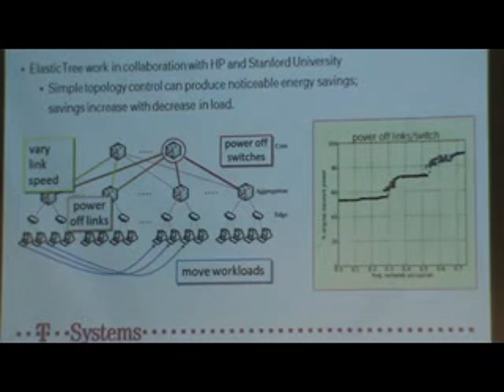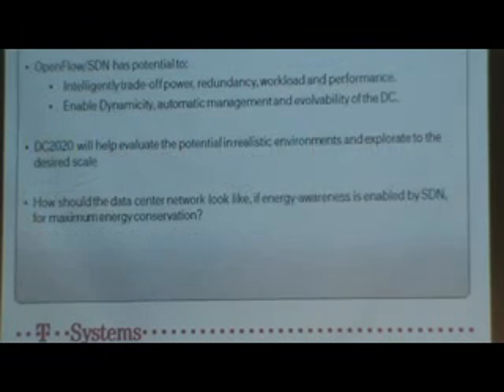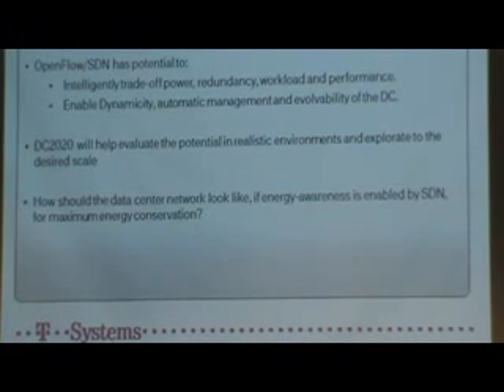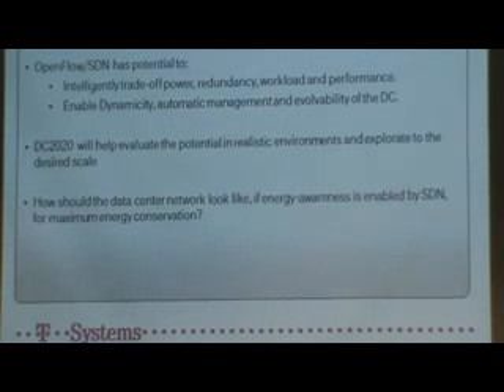And here, by methods of shutting off some links and powering off the links, we have the chance to move workloads in the data center to get to the situation that we have more than 10 kilowatts per rack. The 10 kilowatts per rack is not fixed, but we have to go to higher density in the servers, and that's why it's worthwhile to think about these methods. So, OpenFlow SDN, in my point of view, has the potential to intelligently trade off power, redundancy, workload, and performance, and to enable dynamicity, automatic management, and evolvability of the data center.